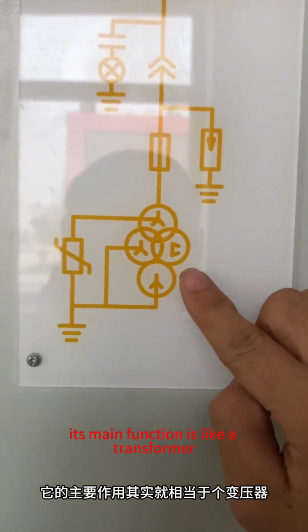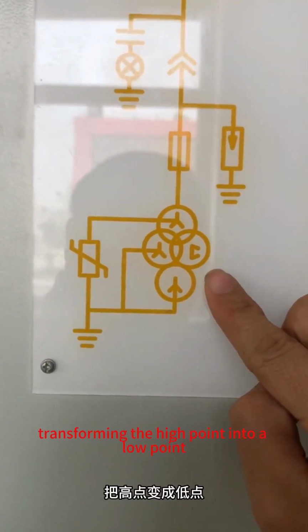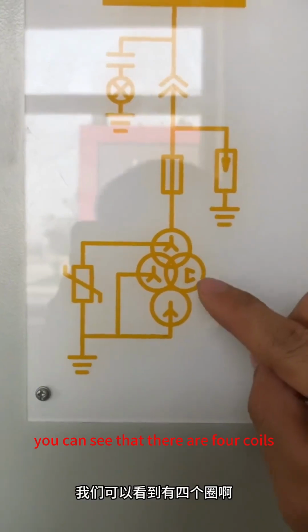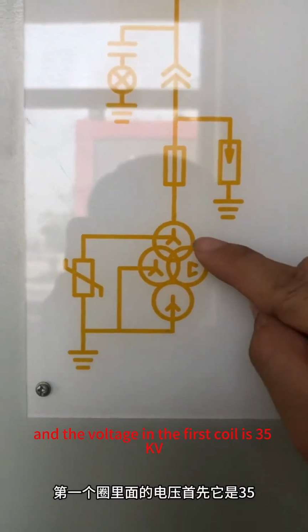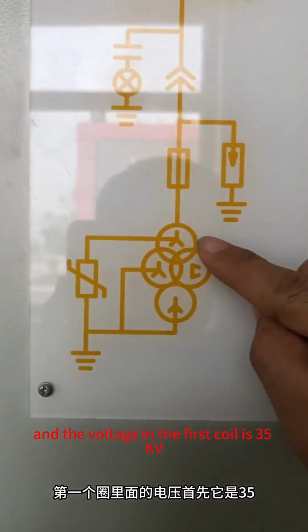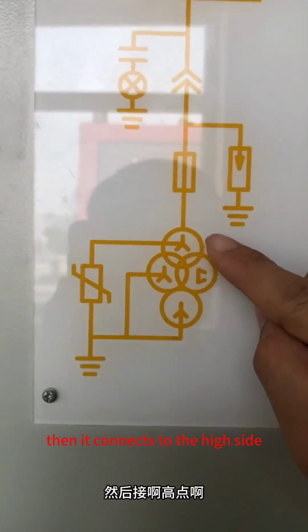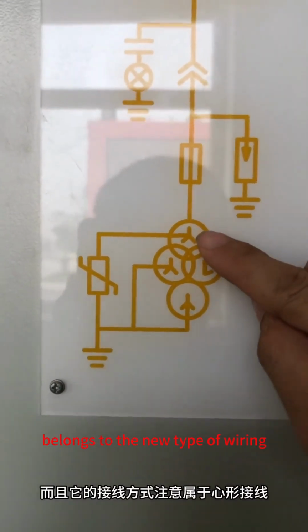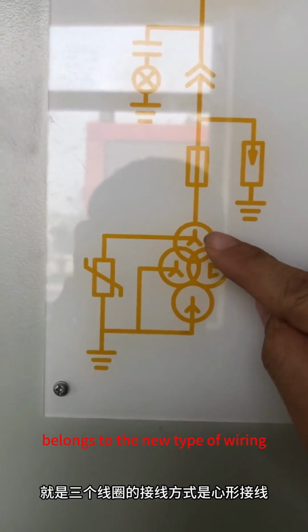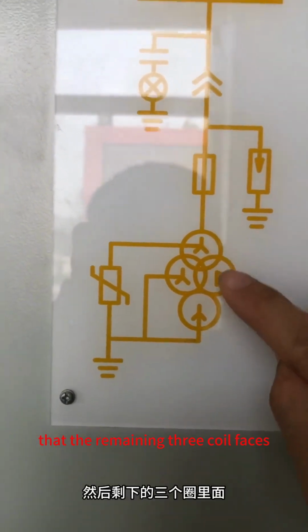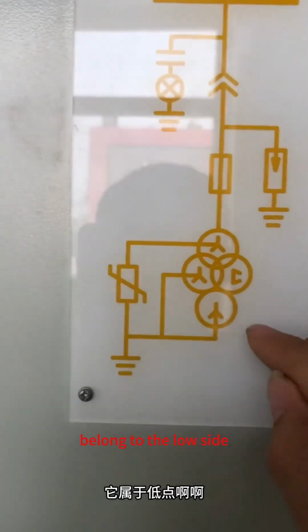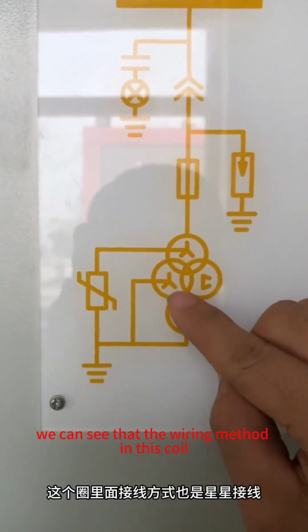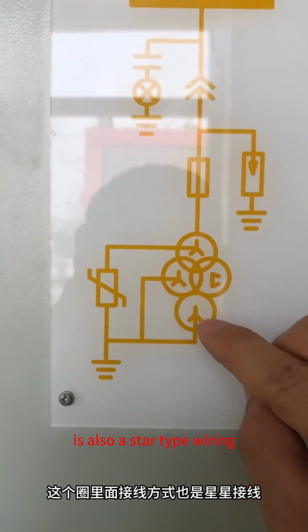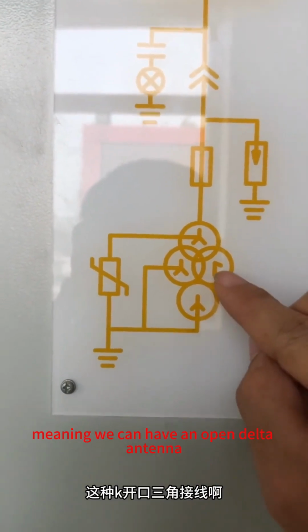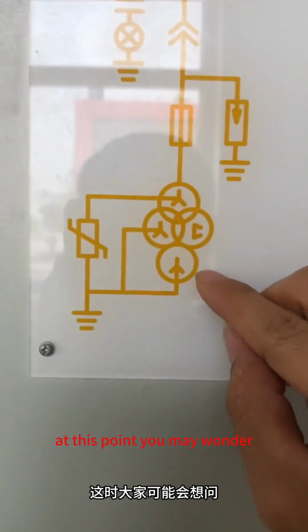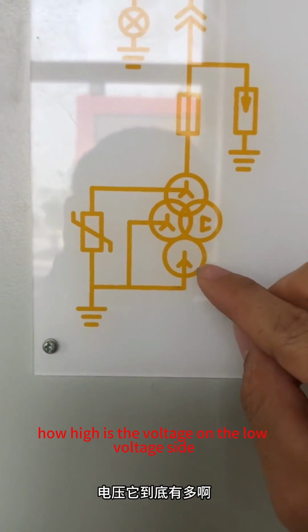Its main function is like a transformer, transforming the high voltage into a low voltage. You can see that there are 4 coils, and the voltage in the first coil is 35 kV. Then it connects to the high side, and its wiring method is star-type wiring, where we can see that the remaining 3 coils belong to the low side. The wiring method in these coils is also a star type, meaning we can have an open delta. At this point you may wonder, how high is the voltage on the low voltage side?